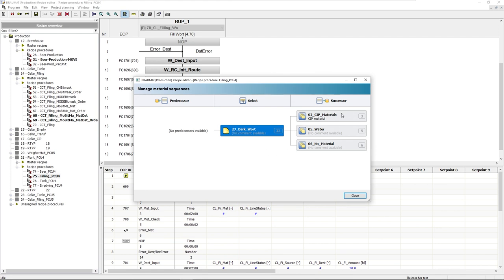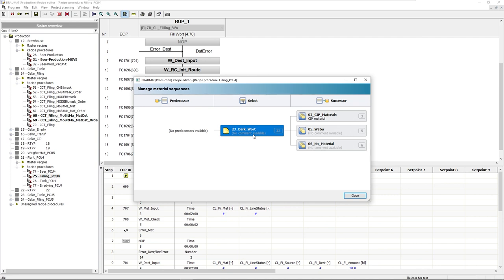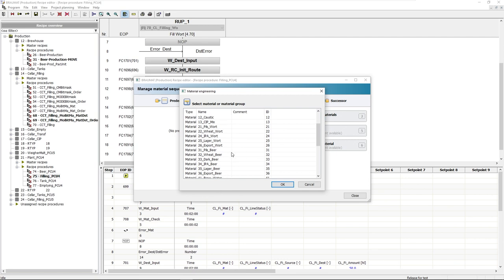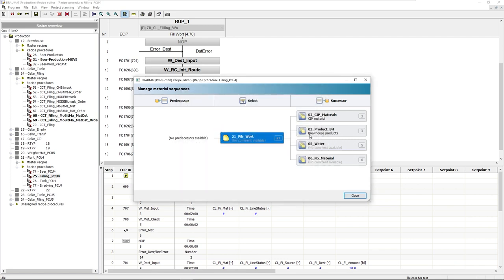So here we see the source material with its successors, possible permitted successors. However, there is also the rule where you can enter the predecessors here. Let's look at an example. If I add dark wort in a pipeline and then use the same pipeline for light wort afterwards, I obviously don't want the color to be distorted. Therefore, after dark wort, I only allow cleaning material, water or a nothing material, in other words, air. In contrast to a light material, I'll now choose a pilsner wort here, I would allow all other brewery products. After all, unlike in the reverse process, a dark wort as a successor will not become lighter. So those are the global rules.